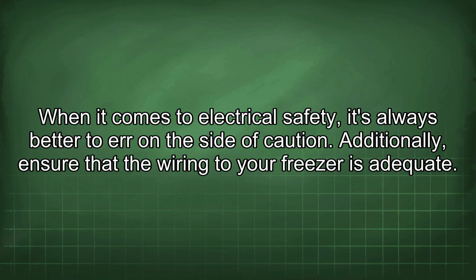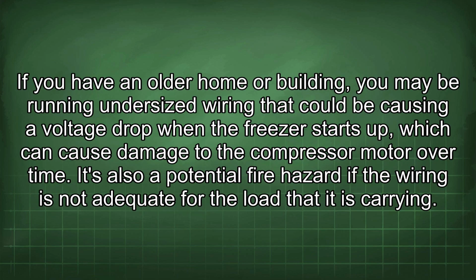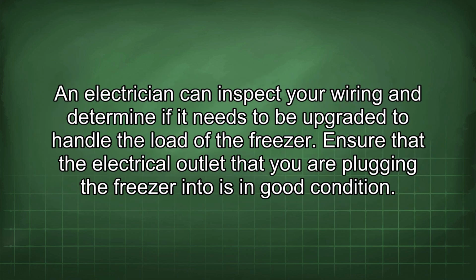Additionally, ensure that the wiring to your freezer is adequate. If you have an older home or building, you may be running undersized wiring that could be causing a voltage drop when the freezer starts up, which can cause damage to the compressor motor over time. It's also a potential fire hazard if the wiring is not adequate for the load that it is carrying. An electrician can inspect your wiring and determine if it needs to be upgraded to handle the load of the freezer.